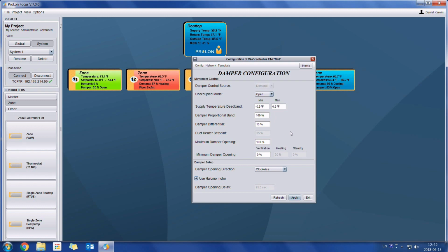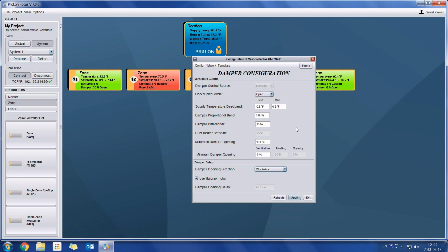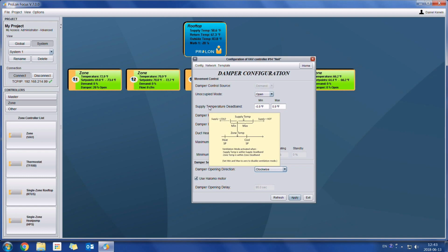So just going through a few of these parameters, we have our minimum damper opening position, our maximum damper opening position, and our damper opening direction, so we don't have to make that change on the controller, we can do it through the software right here. If ever there's a parameter that people aren't sure what it means, or they're not sure how it's going to impact the sequence of the controller, you can always just hover over each line, and there's a little yellow pop-up, which is essentially going to explain what that value means and how it's going to influence the system. So this is going to help you to understand how the controller works instead of always having to go back to the software guides. And as we can see, all the different ones have different explanations, and sometimes we'll even have some with diagrams which will help explain the concept a little bit better.